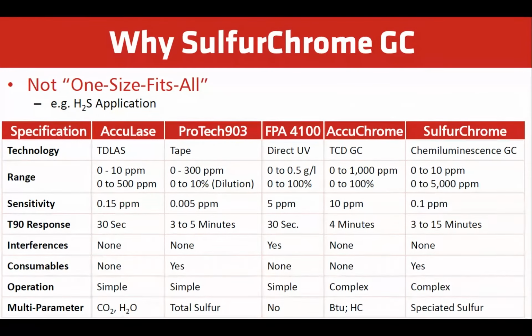The FPA 4100, it's a direct UV. Its range is 0 to 0.5 g per L, 0 to 100% range for H2S. Sensitivity on this analyzer is 5 ppm. T90 response is 30 seconds. It does have interferences. Consumable, there's none. Operation is simple. Multi-parameter, no. The Accuchrome is a TCD GC-based analyzer. Its range is 0 to 1,000 ppm or 0 to 100%. T90 response time is 4 minutes. Interference, there's none. Consumable, none. Operation is complex. Multi-parameter: BTU and hydrocarbons.